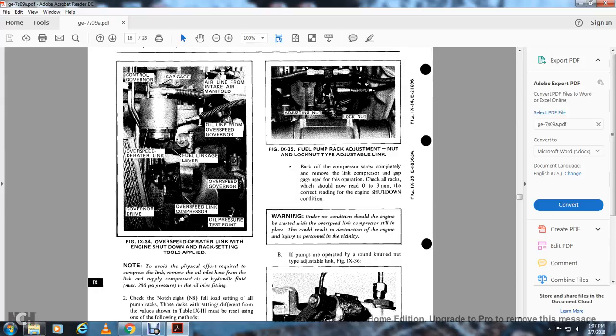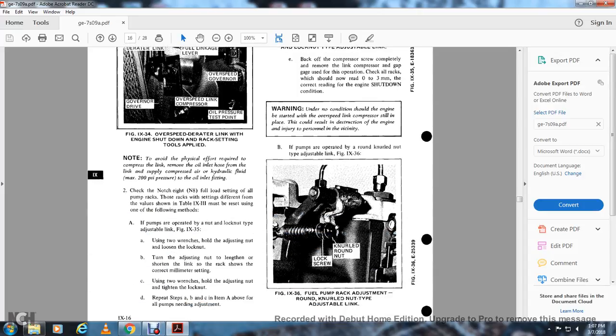Figure 9-35 shows the fuel pump rack adjustment nut with the lock nut type adjusting link. Back out the compressor screw and completely remove the link compressor gap tool used in the operation. Check all racks — they should now be within zero to 3 millimeters of the correct reading in the engine shutdown condition. Warning: under no condition should the engine be started with the overspeed link compressor still in place; this could result in destruction of the engine and injury to personnel in the vicinity.